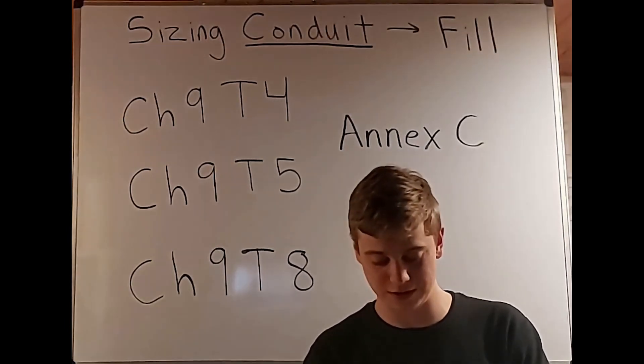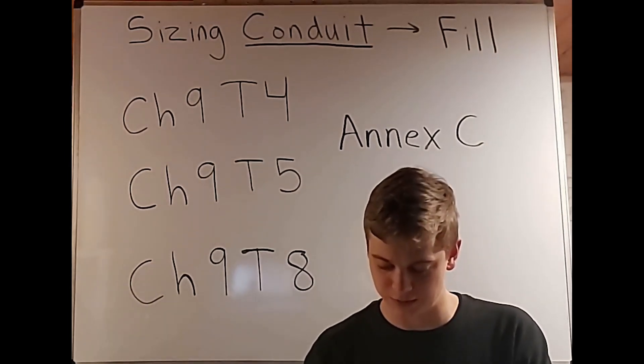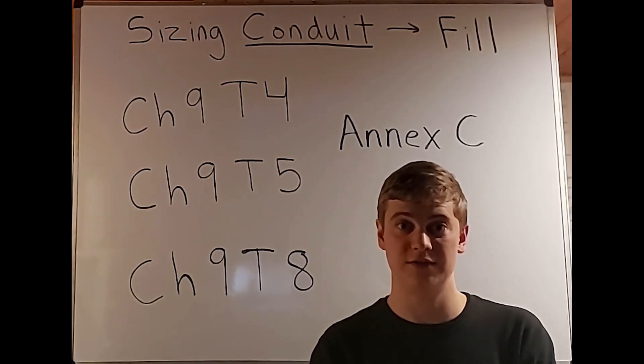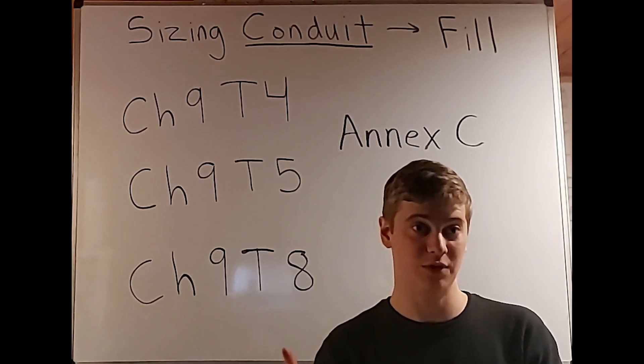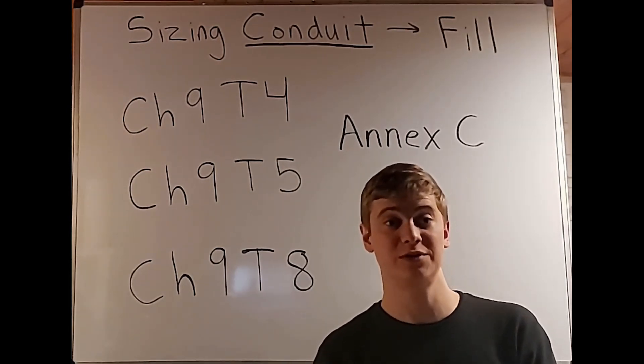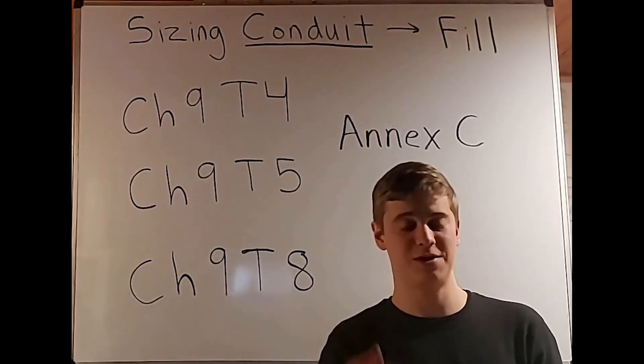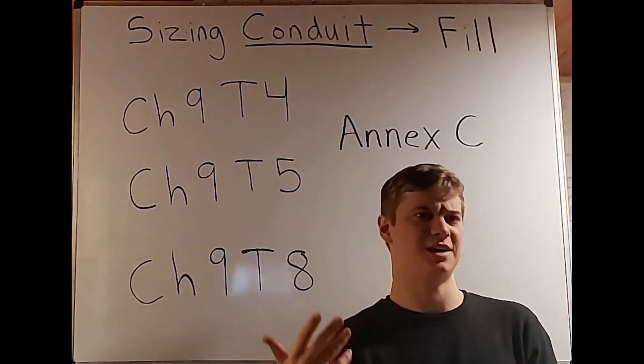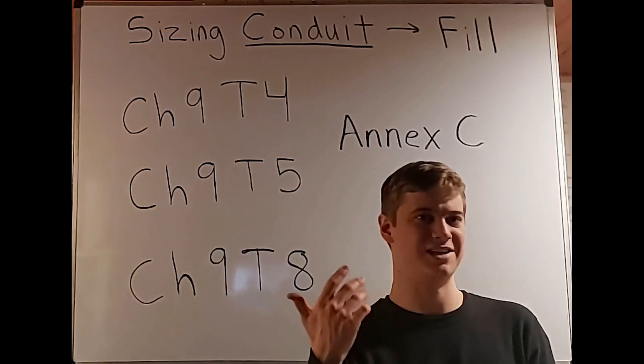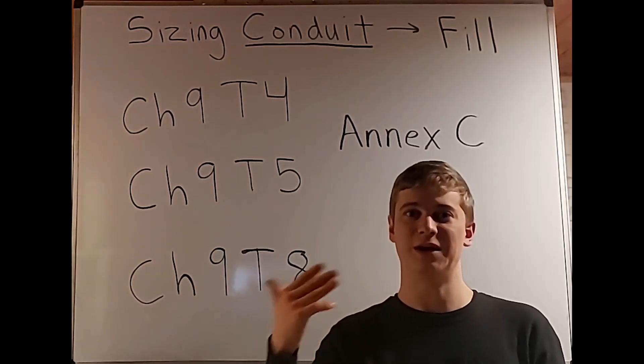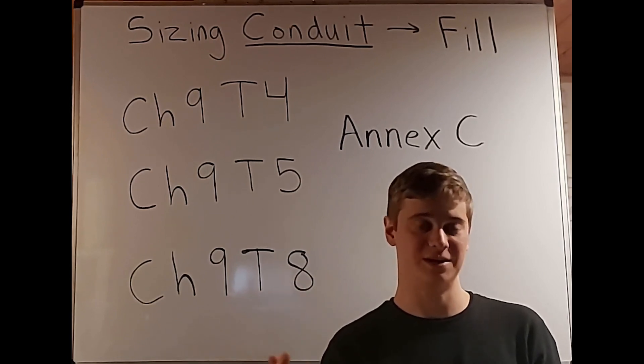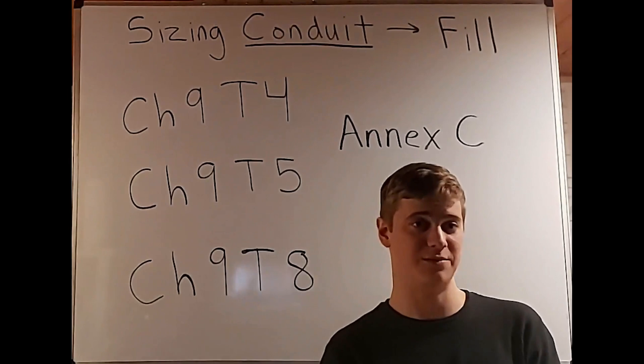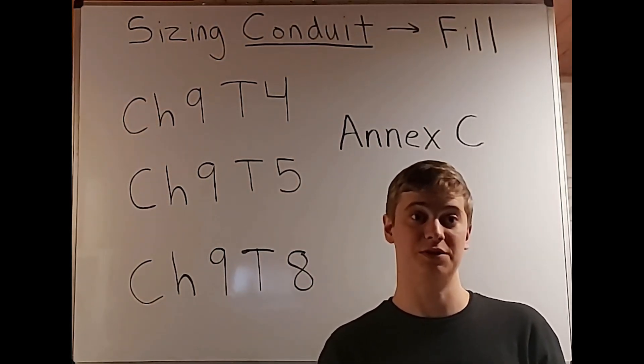The next really important note is number 8: where bare conductors are permitted by other sections of this code, the dimensions for bare conductors in Table 8 shall be permitted. So when you have a question talking about bare conductors, you're able to use Chapter 9, Table 8 to figure out your dimensions — whether that's circular mills or square inches. You'll get a question mentioning a bare conductor for conduit fill, and you'll need to know its size. That's where Chapter 9, Table 8 comes in — often you'll be using square inches, but it's also the table for circular mills.